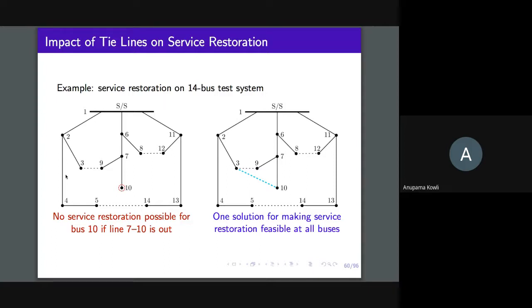If I were to lose this link because of a fault, nodes 4 and 5 would not be completely restored until I energize, by closing, this normally open switch between 5 and 14. Does that make sense to everybody? As the other person pointed out, if there was a fault on 2-4, the entire feeder would be de-energized first, then 2-4 would be isolated, and supply would be restored here by switching on the 5-14 normally open switch. Does everybody see this?